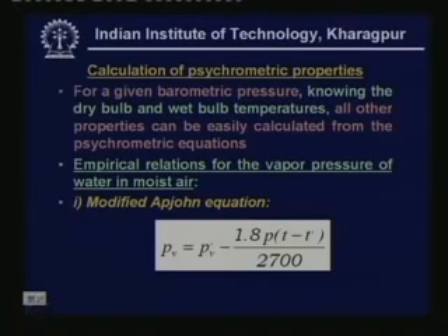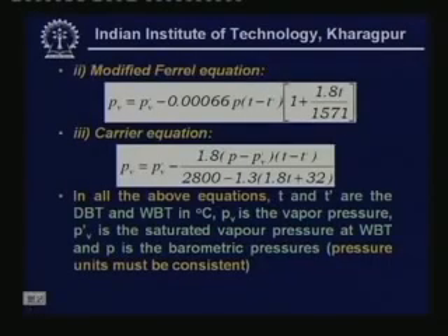So this is one of the empirical relations using which one can find the vapor pressure. For example, here we know the dry bulb and wet bulb temperatures from the psychrometer readings. Then we can find P dash V, which is nothing but the saturated vapor pressure, using steam tables or equations for saturated steam. Then the barometric pressure is anyway known. The next empirical equation is what is known as the modified Ferrel equation. This equation is given by PV equals P dash V minus 0.00066 P into (T minus T dash) multiplied by (1 plus 1.8 T by 1571). Again here T and T dash are dry bulb and wet bulb temperatures, P is the barometric pressure, and P dash V is the saturated vapor pressure at wet bulb temperature.